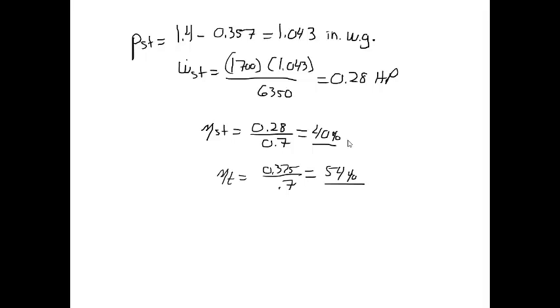So basically this problem was just to get you to learn how to use the equations associated with a fan. You have static pressure, which is the pressure that the fan needs to produce in order to overcome, in order just to start the fluid flowing. Then you have the velocity pressure, which is the pressure above static pressure that gets the fluid velocity to flow.